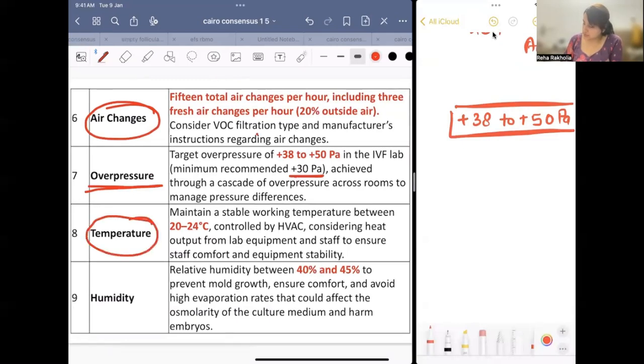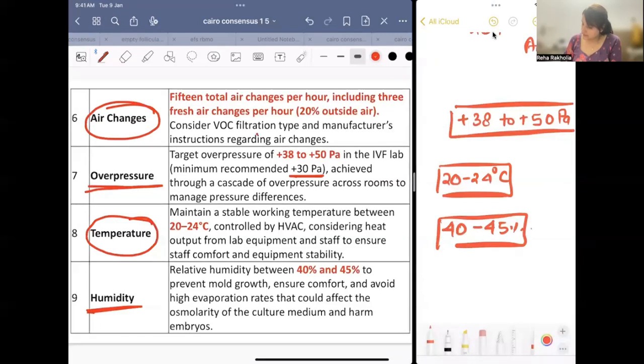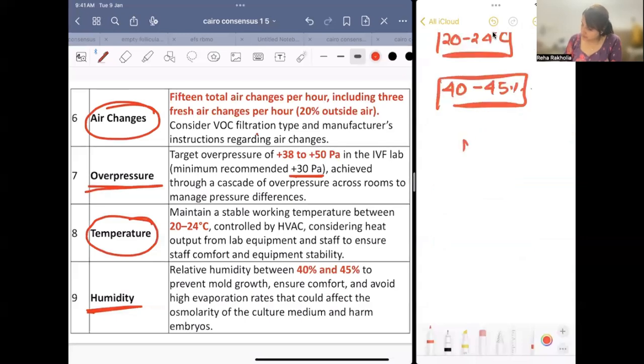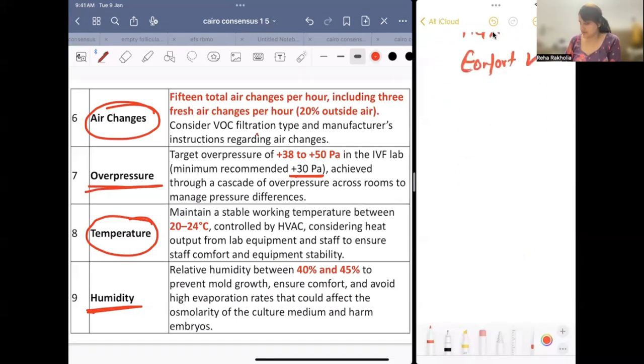Temperature should be maintained at 20 to 24 degrees Celsius. Humidity should be maintained between 40 to 45% to avoid mold growth, to ensure comfort, and to avoid a high evaporation rate that could affect the osmolarity of the culture medium, so that it does not harm the embryo.